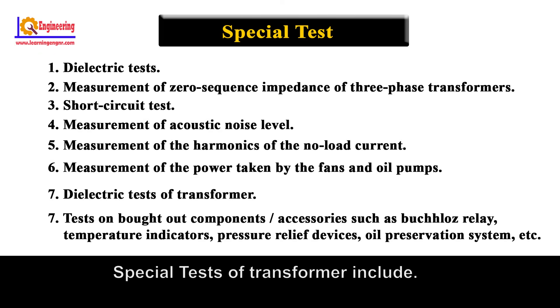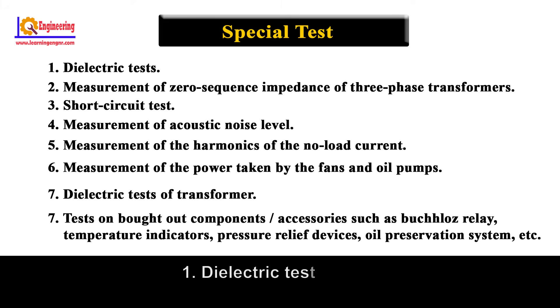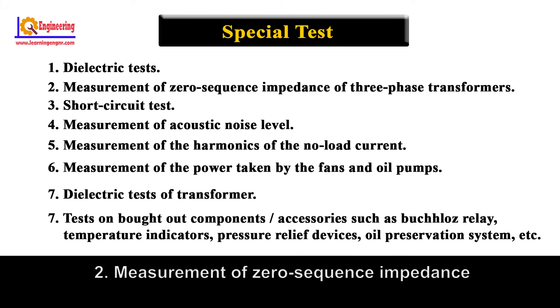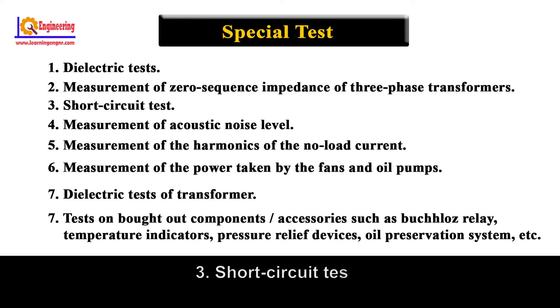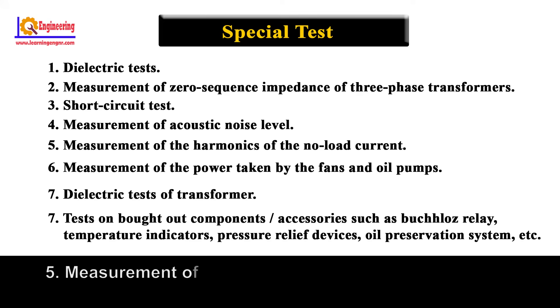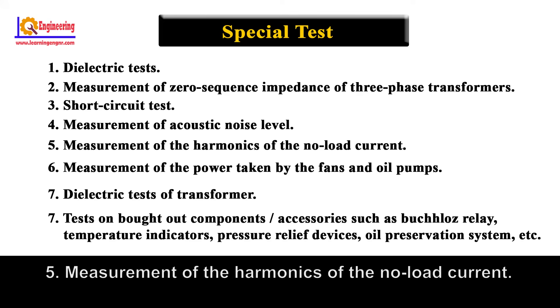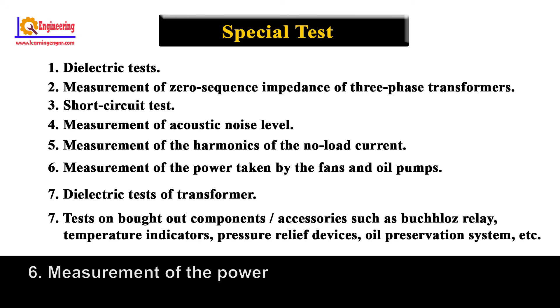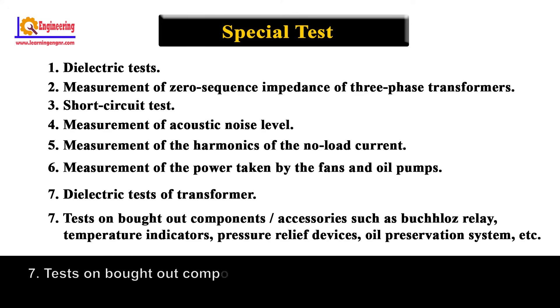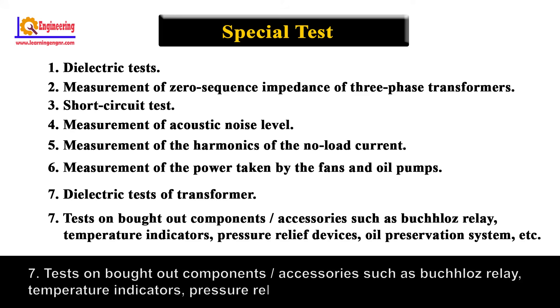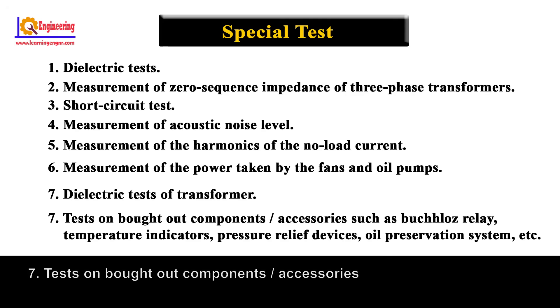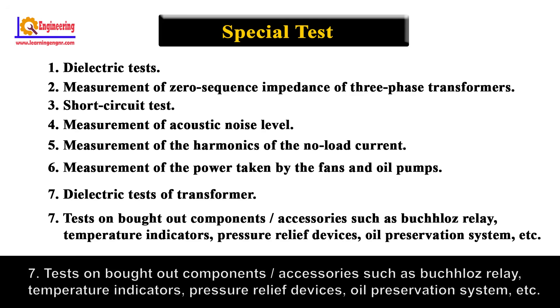Special Test of Transformers includes: Number 1, Dielectric Test; Number 2, Measurement of Zero Sequence Impedance of Three-Phase Transformers; Number 3, Short Circuit Test; Number 4, Measurement of Acoustic Noise Level; Number 5, Measurement of the Harmonics of the No-Load Current; Number 6, Measurement of the Power Taken by the Fans and Oil Pumps; Number 7, Test on Bought-Out Components or Accessories such as Buchholz Relay, Temperature Indicators, Pressure Relief Devices, Oil Preservation System, etc.